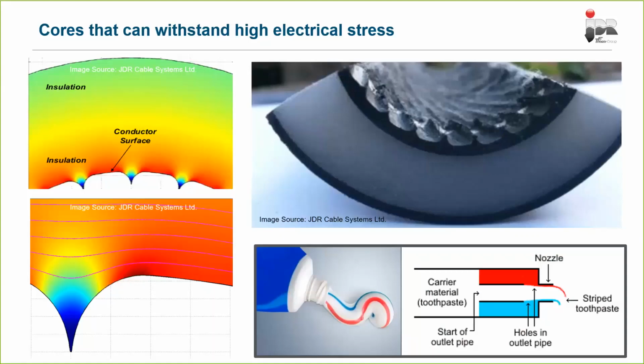So what we do is we put in this extra layer on either side of the insulation, and this layer is applied over the conductor, and you can see there, and it offers a very smooth surface for the insulation layer, which is here to go on. So this layer and this layer is semiconducting, and we apply them in a triple extrusion operation. So if we had a power core, we could apply this in one operation, then this in another operation, and then this in another operation, so stagger them out. However, the insulation layer is critical in a power core, so we want to ensure there's minimal chance of any contamination getting into those 3 sections. So we apply it through this triple extrusion method, which means that the 3 layers are applied in one operation, similarly to how toothpaste is produced. Okay.